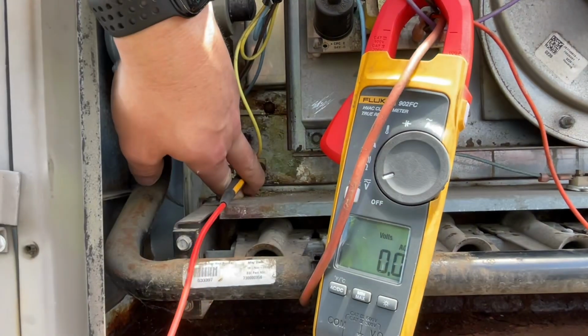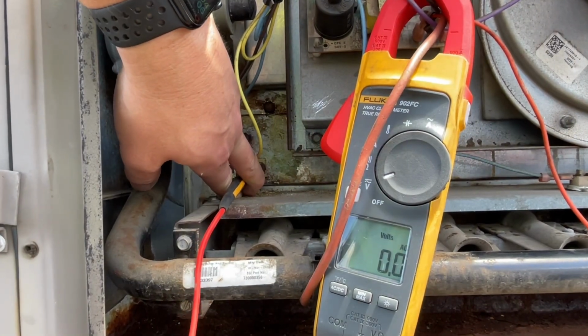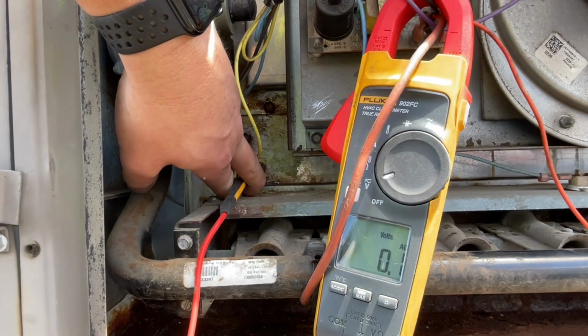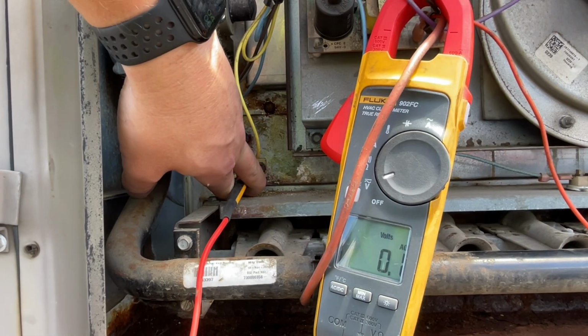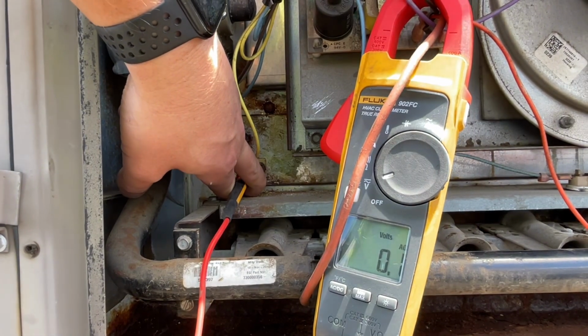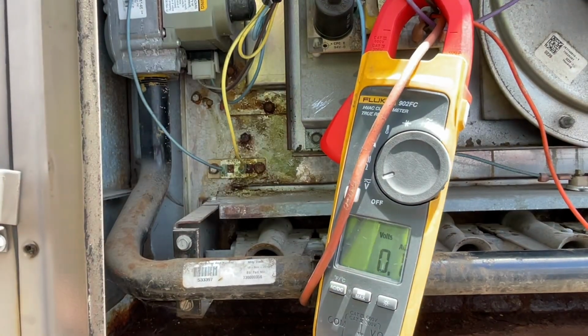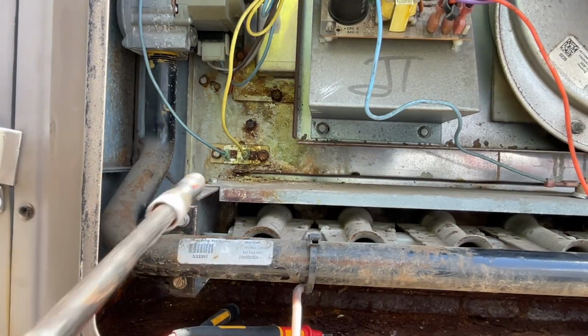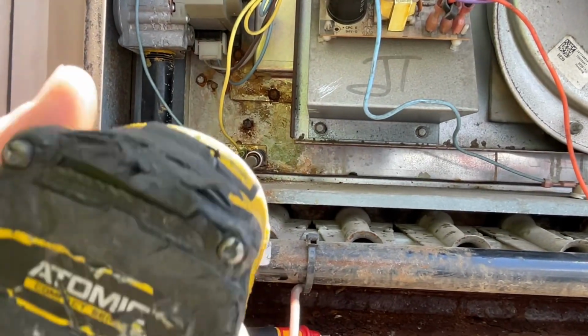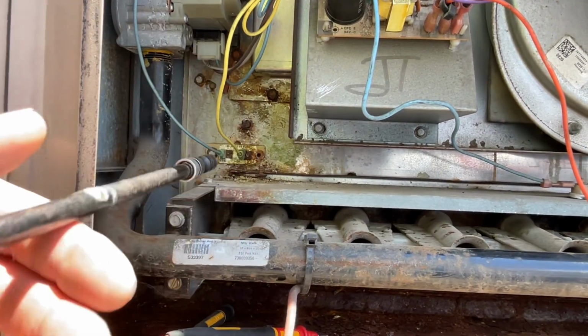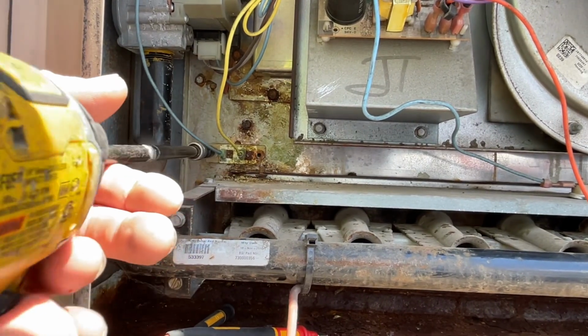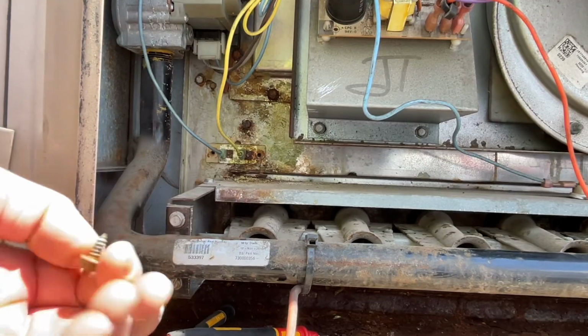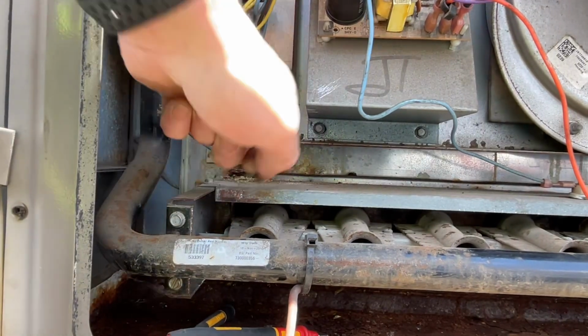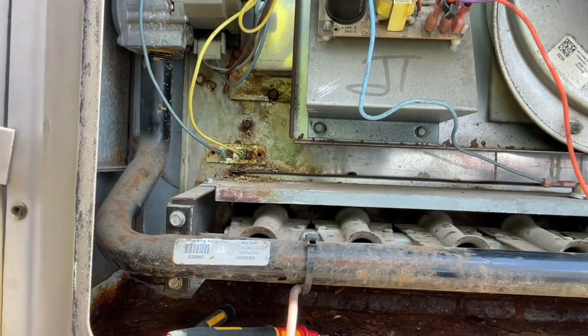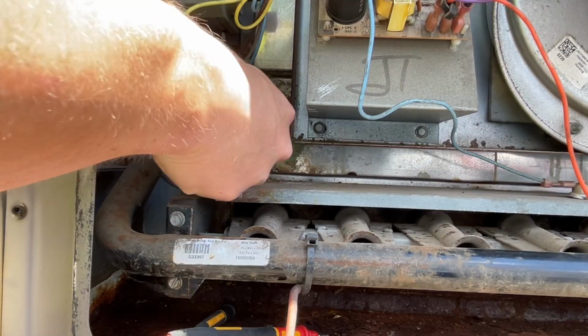What we're gonna do though is we're gonna pull these spades off and check through our spade connections, because I don't trust that limit switch. So we'll shut the power off and we'll ohm out this safety next, and then we'll jump it out just to verify that inducer motor shuts off. Our power's off now. Let's see if we can get this limit switch out. That's in awful shape. That is in awful shape. And this is what it'll look like.